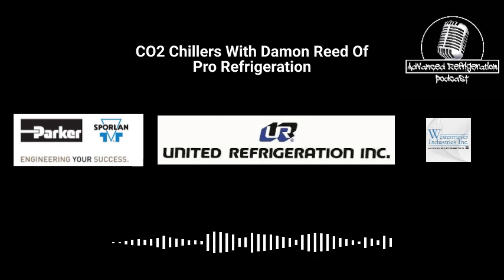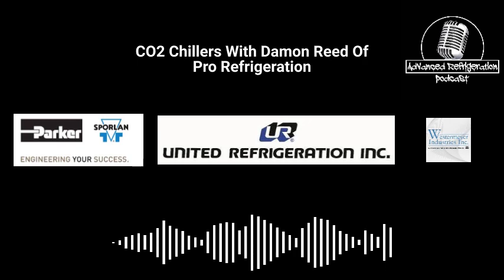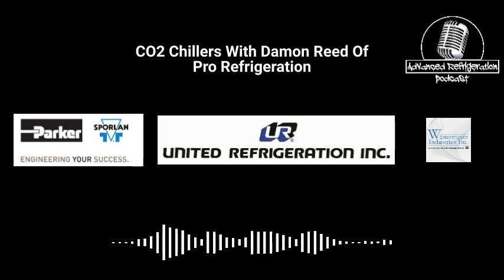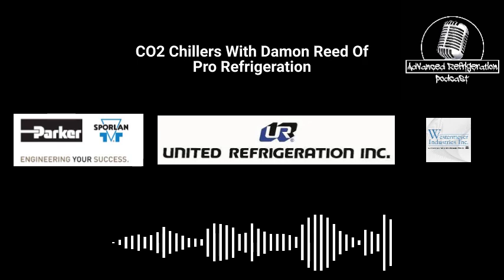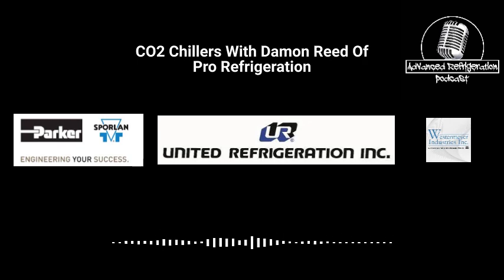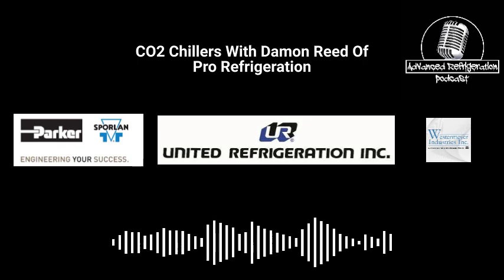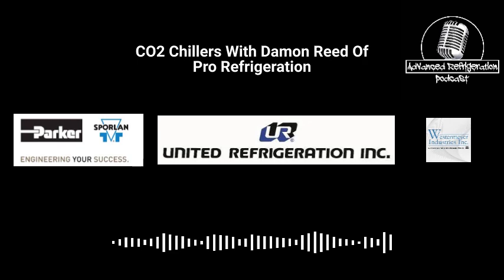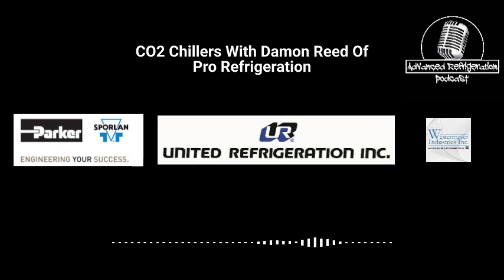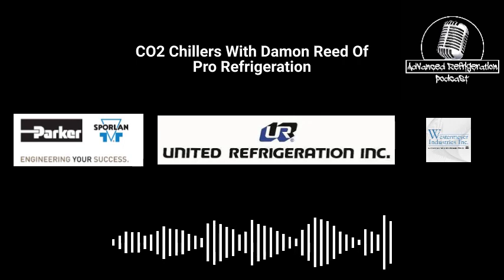Hey, unsung hero. With our customer, our first system that's in down there, we measured and quantified what we're doing. We keep hot water heaters in parallel with the swing tanks, but the swing tanks are getting heated by the heat recovery system. So we were able to take one of their heater systems and shut it off completely. And we measured the amount of gas savings on propane. For that customer, it was 41 gallons of propane per day. Holy shit. Wow, that's a lot.